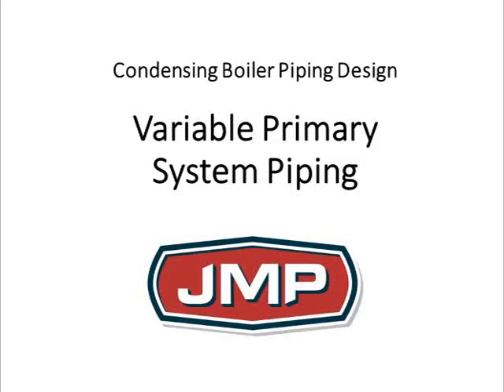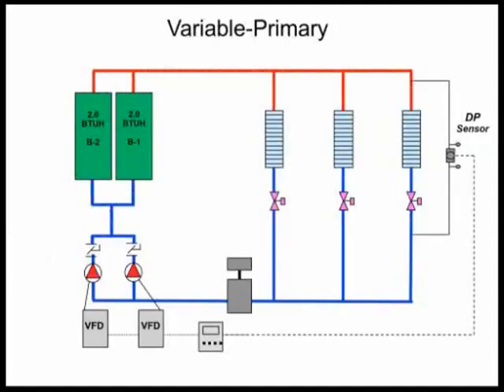Variable primary. What does a variable primary system look like? Here's a good example: a couple of boilers, a couple of variable speed pumps, an air separator, expansion tank, and some coils. People started designing systems this way so that the boilers always saw the lowest return water temperature. This arrangement can also save you some pump energy because you have variable flow from one end of the system to the other.